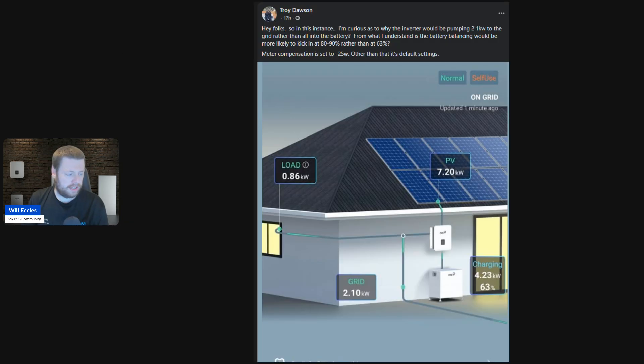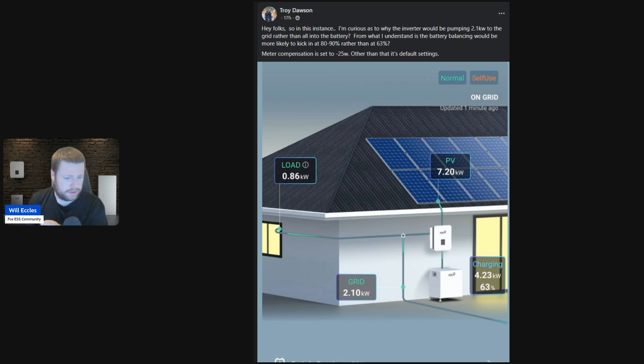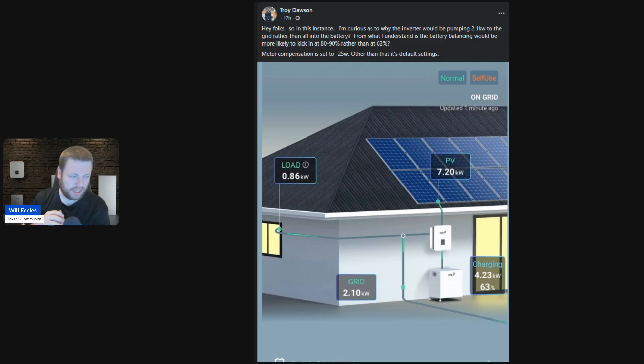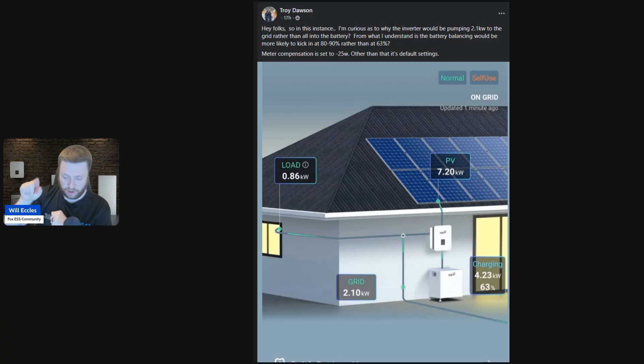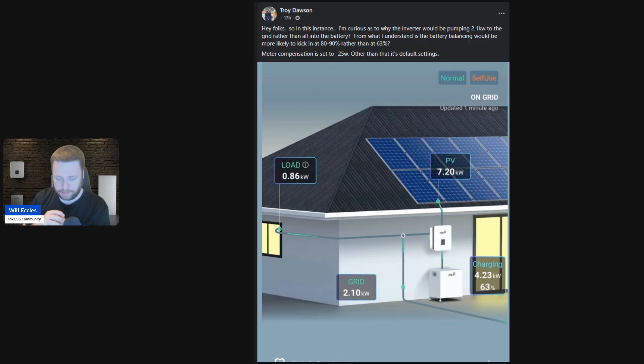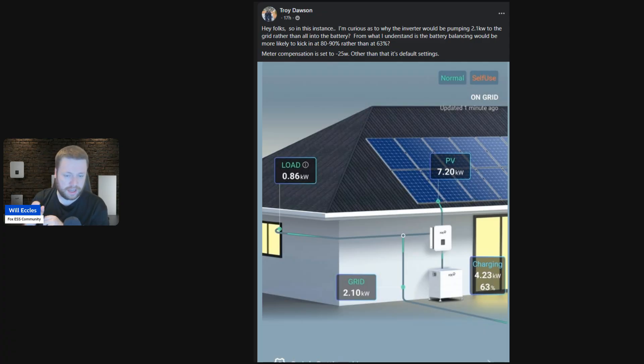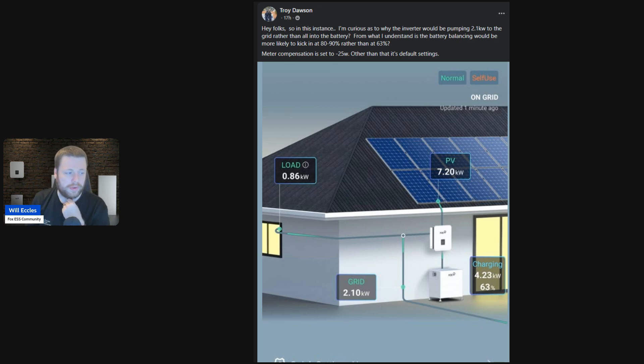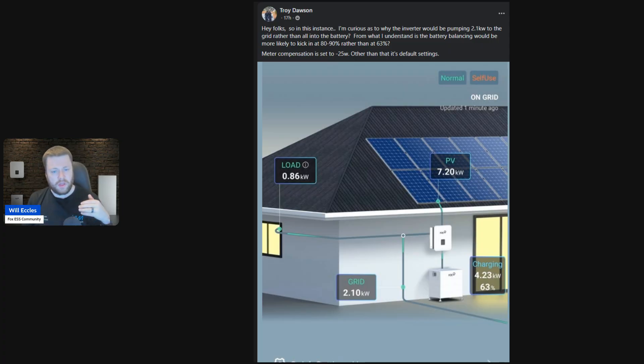So what is probably happening if we go back to this? We go back to the image that Troy shared. If it's not temperature or state of charge, it's probably the battery configuration. You'll be able to tell this by looking at what the battery voltage is, either on the inverter screen or if you drill into the chart. One of the options is battery volts. You can see what the battery voltage is and just use this tool, this Rapid Tables, times your current of say 25 amps times that by the voltage that you see on the app, and I wouldn't be surprised if you see something like this rating.